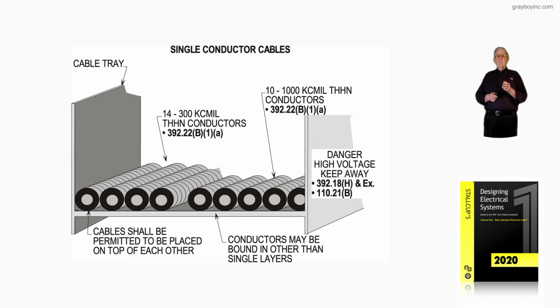Danger, high voltage, keep away, in accordance with 392.18(H), an exception. And if it's up high where no one can reach it, then the exception would apply, and it indicates that you might not need that high voltage rating, but it's good to have that always on a high voltage type tray so people will know that high voltage is in that cable, over 1,000 volts, and to apply extreme care.